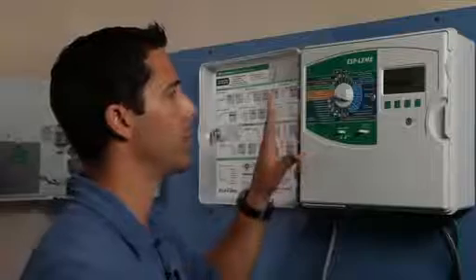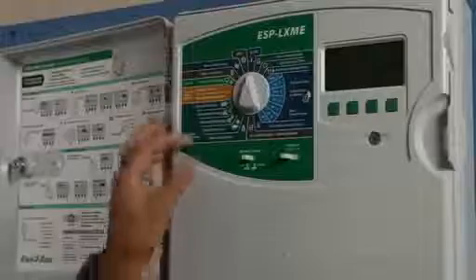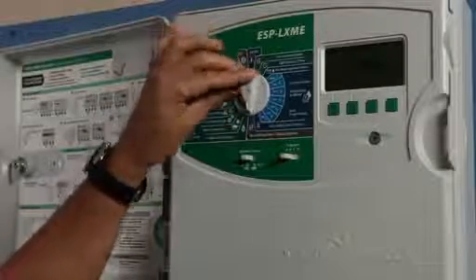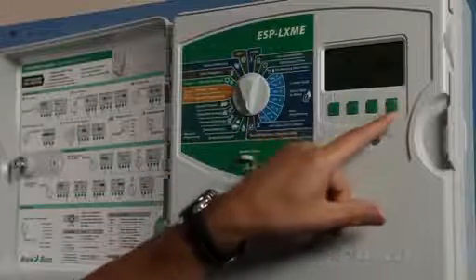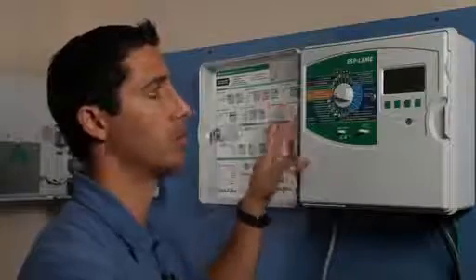One feature we really think speeds up the implementation of flow sensing on this controller is the fact that they've got pre-programmed k-factor and offsets into the controller. So we simply enable flow sensing and select the flow sensor we want to use, and we don't have to spend time plugging in those numbers. They're already there for us.